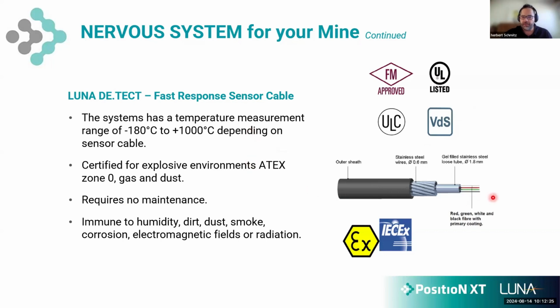We spoke a little bit about the sensor cable. This is its construction. We have 4 fiber optic cores in there, stainless steel tube, stainless steel wire armoring, fully fire certified, extremely robust. Now, our interrogator units can interrogate data theoretically from minus 180 to plus 1000. This sensor cable will be comfortably minus 50 to plus 150 and carry certification for explosive dust and gas environments.